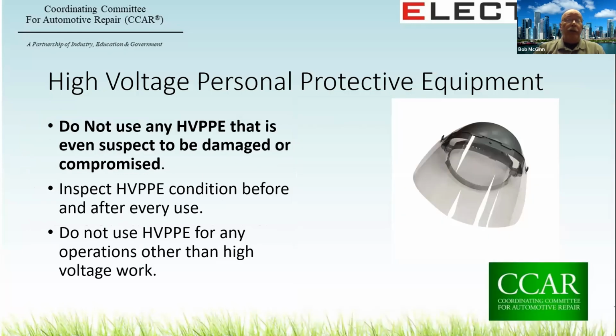As a best practice, don't use anything that's suspect. Inspect your personal protective equipment frequently. And the best rule that I can apply as a best practice is only use your high voltage personal protective equipment for high voltage work. Segregate it. You have face shields, gloves, any other device that you're using for PPE for high voltage, lock it up when we're not teaching or working in high voltage.